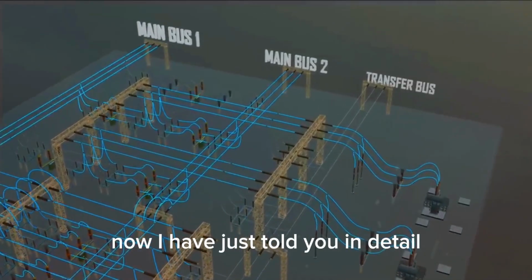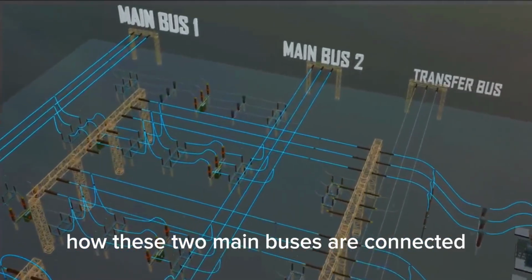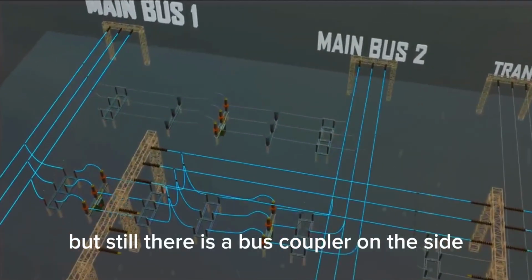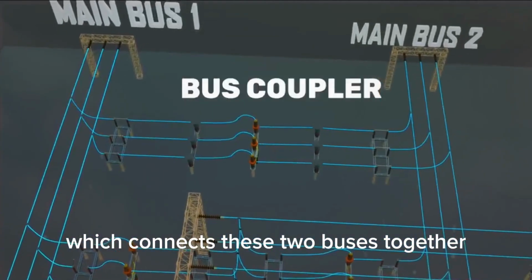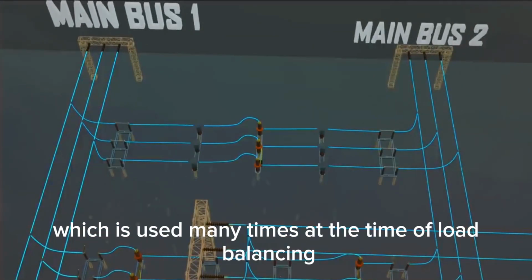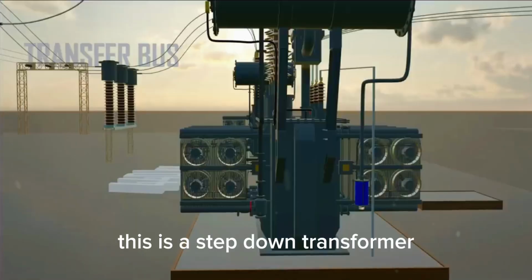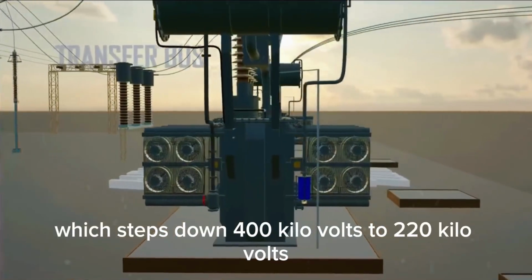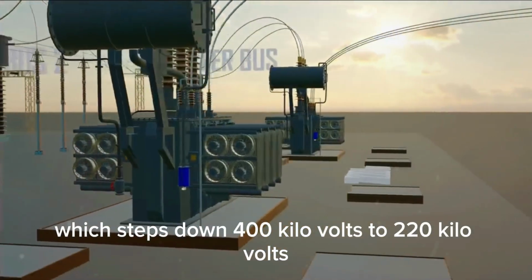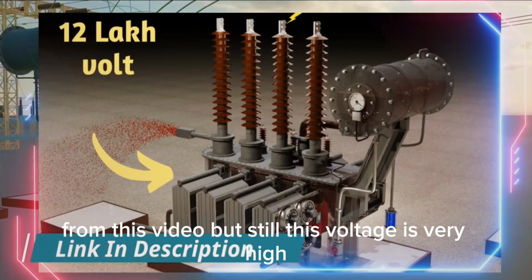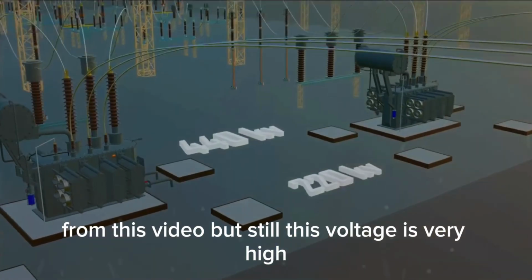Now, I have just told you in detail how these two main buses are connected. But still there is a bus coupler on the side which connects these two buses together, which is used many times at the time of load balancing. This is a step-down transformer which steps down 400 kV to 220 kV. You can see the working of the transformer from this video. But still this voltage is very high.